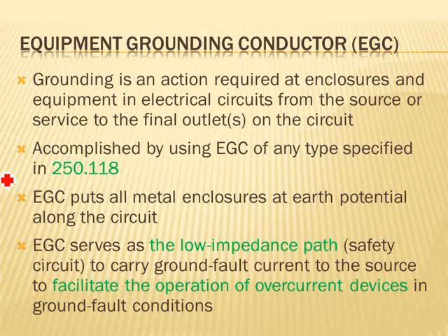Now, if that were to happen, then the hot will touch the frame. The frame is already grounded. Bang! It gives you a low impedance path back to the source. The circuit breaker will wake up before you get electrocuted. That's really the fundamental need for the equipment grounding conductor. That's why you need the low impedance to the ground. Facilitating the operation of the overcurrent device is a big deal, guys.